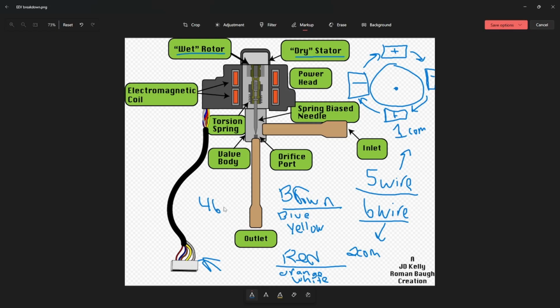Trane expects to see 46 ohms, plus or minus 3, on each coil. So you would expect to see 46 ohms from brown to blue, from brown to yellow, from red to orange, and from red to white. If you see any drastic variance, that usually means a coil has failed. If you lose a coil and it's no longer in the circuit anymore, and it no longer has any electrical charge, it's just dead, your needle will spin here to here to here, and once it hits this, it just stops. When it hits that point, it's not going to do anything because there's a dead spot right here. There's no charge, positive or negative, to move that little rotor past this point.